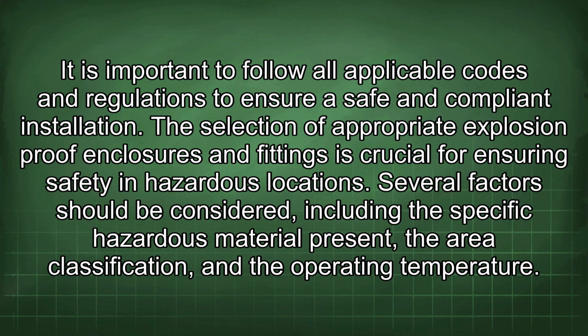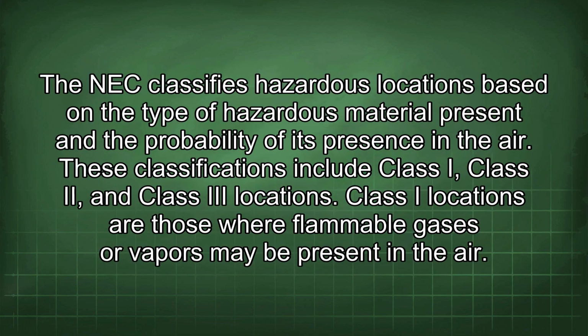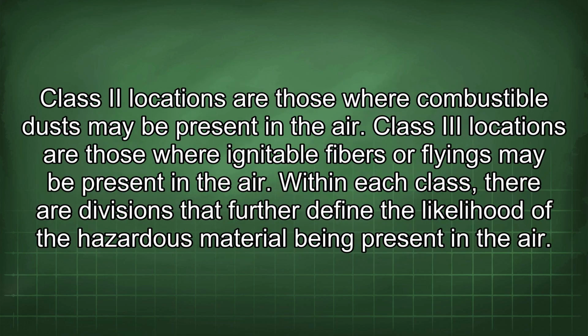The selection of appropriate explosion-proof enclosures and fittings is crucial for ensuring safety in hazardous locations. Several factors should be considered, including the specific hazardous material present, the area classification, and the operating temperature. The NEC classifies hazardous locations based on the type of hazardous material present and the probability of its presence in the air. These classifications include Class I, Class II, and Class III locations. Class I locations are those where flammable gases or vapors may be present in the air. Class II locations are those where combustible dust may be present in the air. Class III locations are those where ignitable fibers or flyings may be present in the air.